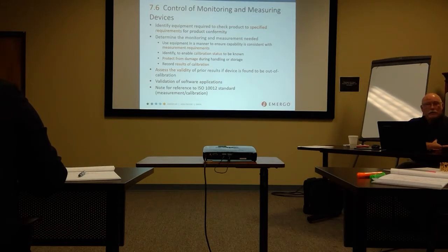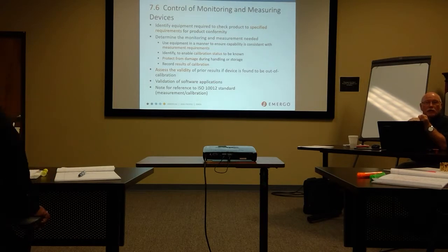I file that, it's all good. If you do this in-house, then you have multiple other requirements. You have to have a calibration procedure. How do I calibrate this thing? Using what? The standards that I'm calibrating against have to be NBS traceable, which means you have to buy them, and they have to be calibrated against something else routinely. The people that conduct this service need to be specifically trained, and that training needs to be documented.